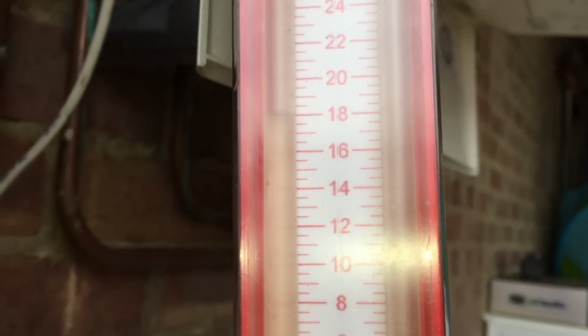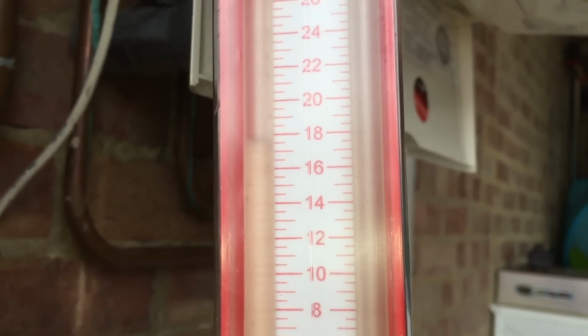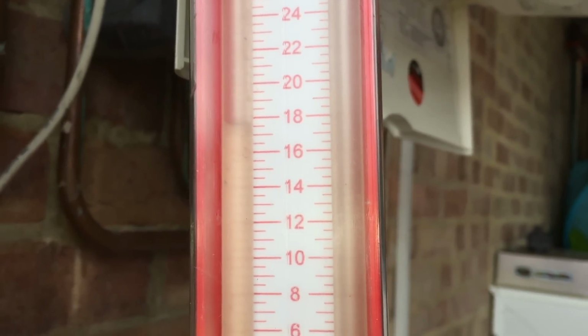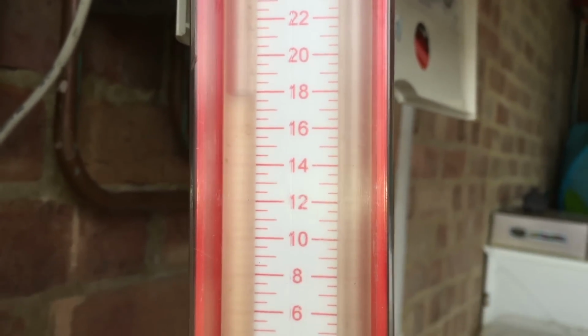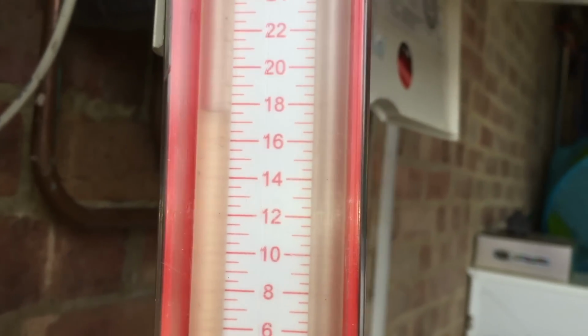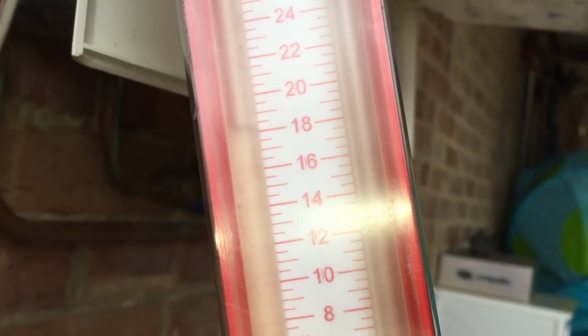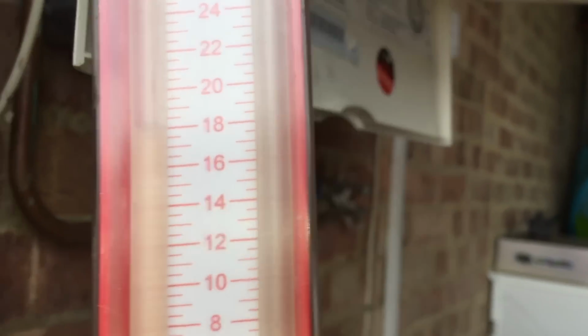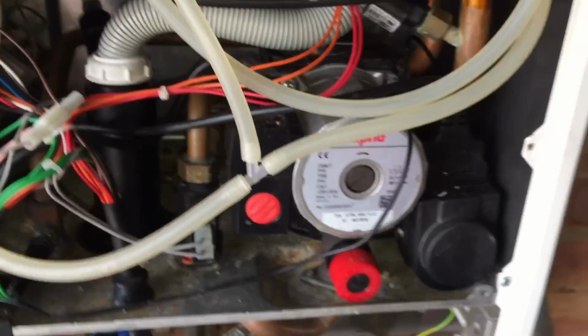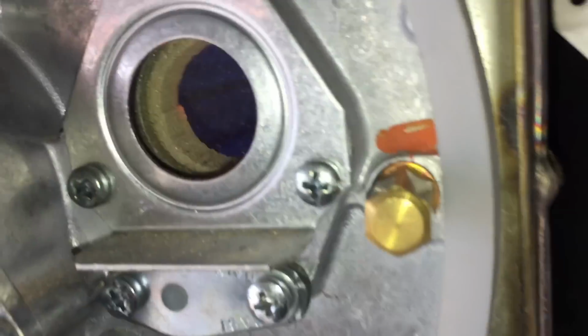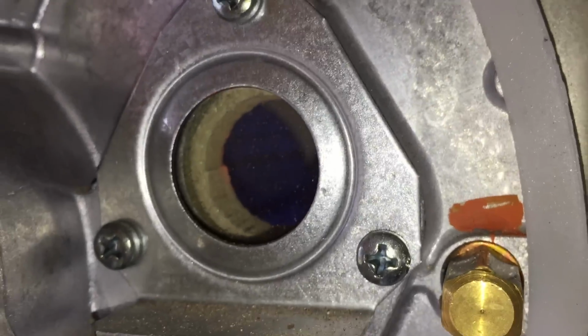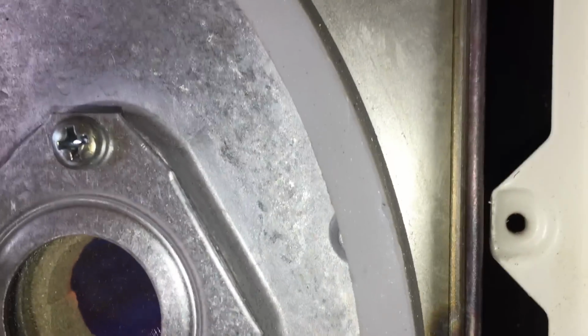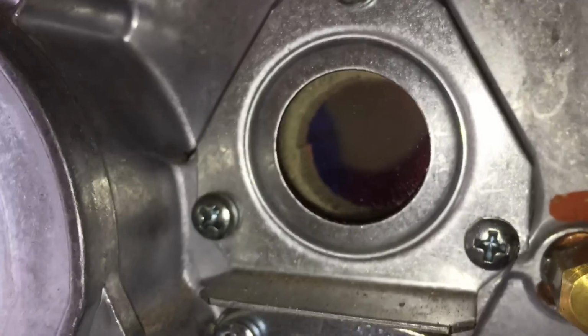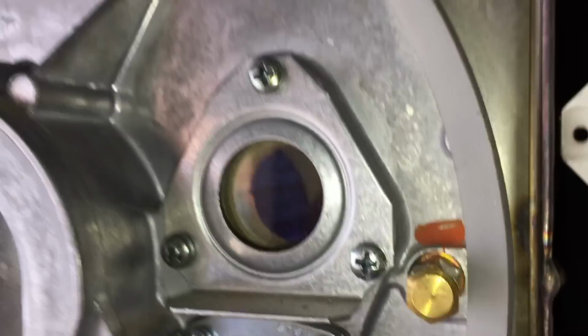After their magic, we have 18 millibar. It's been fluctuating between 18 and 19. It's bouncing a bit down now, but you know, if we do this, there you go, 18 millibar. And they've got hot water. The flame picture is still, I mean, it's okay. I'll take a photo of it, you'll see it better. It's okay, but I bet it's not going to be great on a combustion analysis.